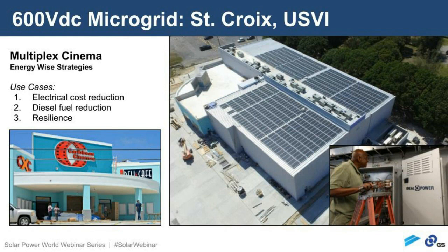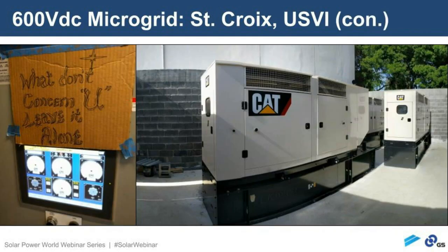The diesel generators have their own operating parameters. They are essentially autonomous; their controller determines which generator runs on a daily basis. But they're called into play by the energy management system, which also determines when a generator might form the grid versus the solar inverter forming the grid.